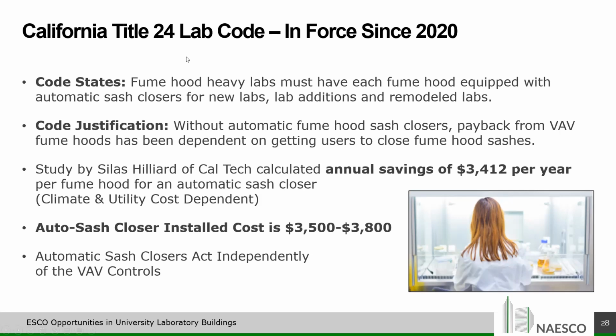One more thing about the auto sash closer: it is a completely standalone project. If you run into a laboratory space that may have a functioning VAV system, auto sash closers are completely independent. They are standalone, so they can be mixed and matched with whatever system is currently out there. We just ensure that that sash door gets closed and that the VAV system is working to its optimal capability.